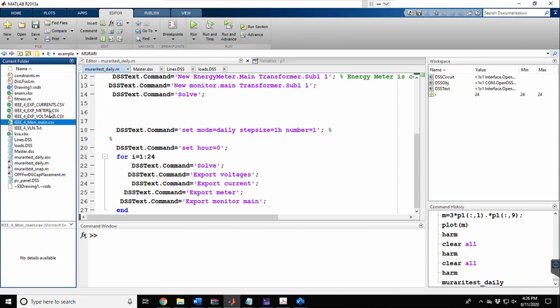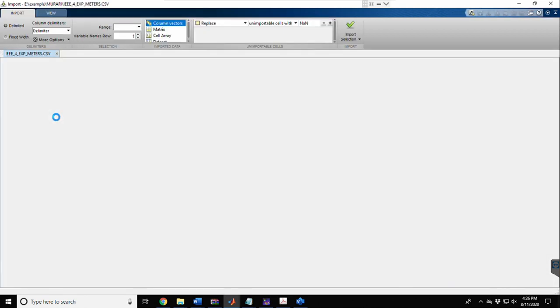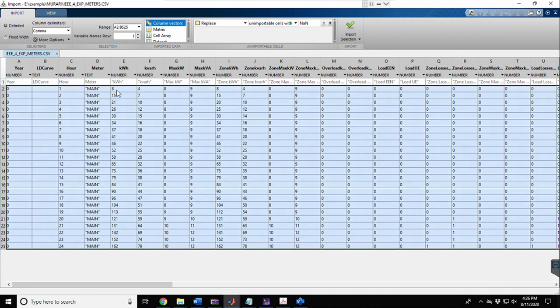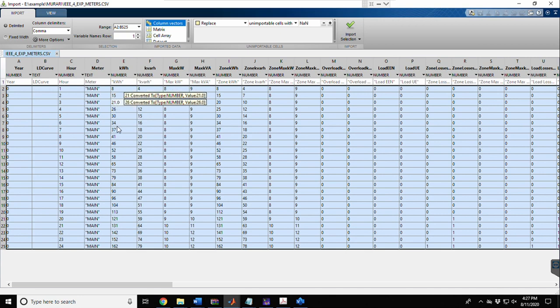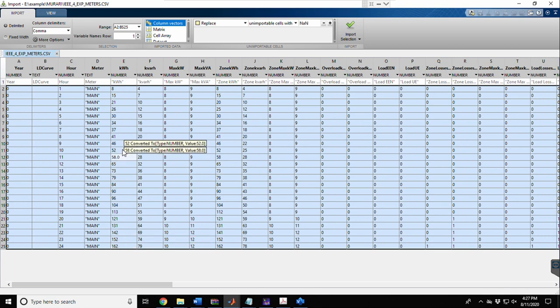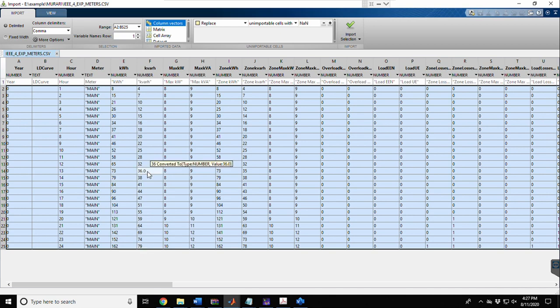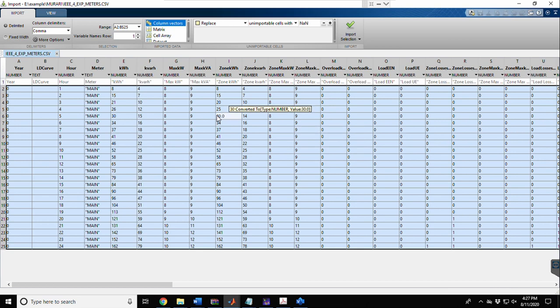This is the energy meter output file. It provides energy in kWh: the energy starts at 8 kWh and keeps increasing as it integrates, reaching a total of 162 kWh at the end of 24 hours. It also gives reactive energy in kVArh, which similarly increases to 79 kVArh at the end of the daily load flow. Peak load at each time interval is also given. Refer to the OpenDSS manual for more extensive use of the energy meter.